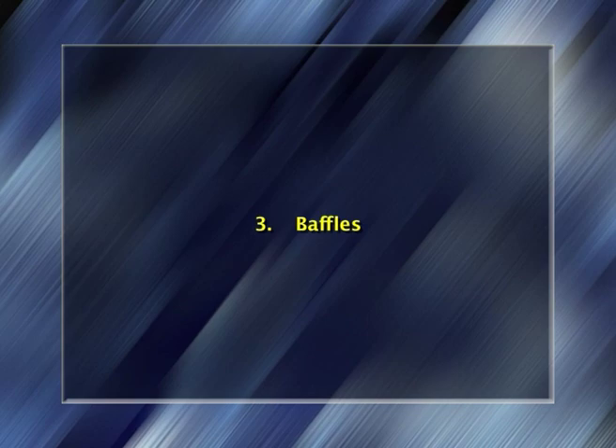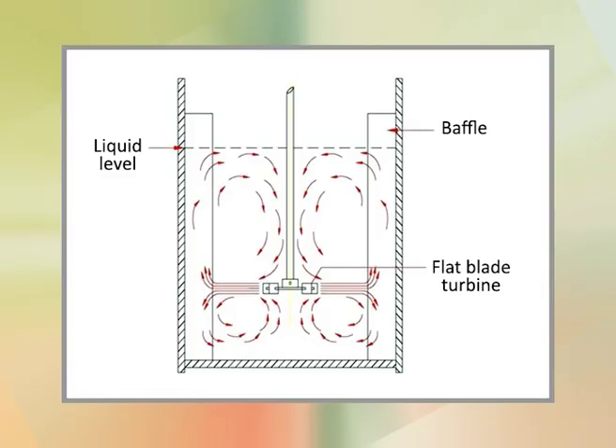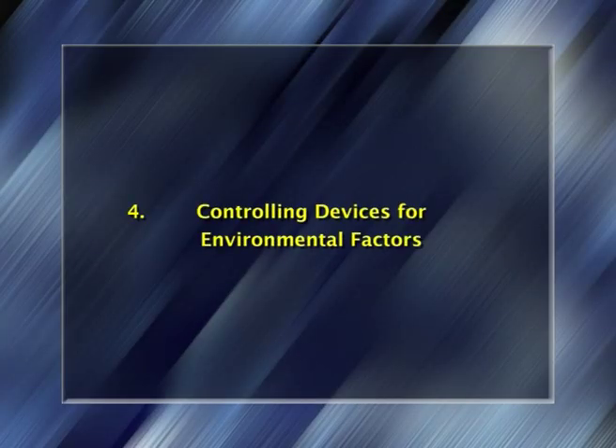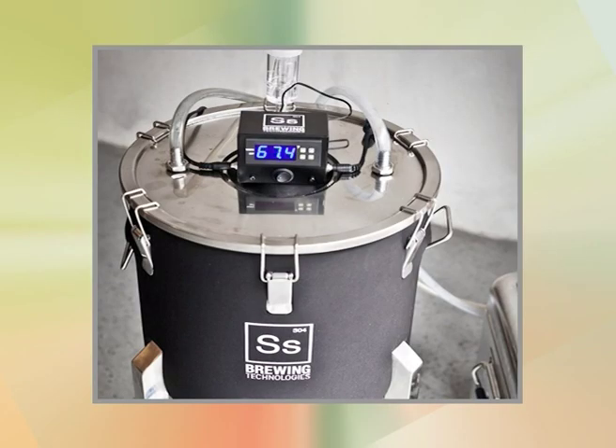Baffles are normally incorporated into the fermenter of all sizes to prevent a vortex and to improve aeration efficiency. They are metal strips roughly one-tenth of the fermenter's diameter and attached radially to the walls. Controlling devices for environmental factors: in any microbial fermentation, it is necessary not only to measure growth and product formation but also to control the process by altering environmental parameters as the process proceeds. Environmental factors that are frequently controlled include temperature, oxygen concentration, pH, cell mass, level of key nutrients, and product concentration.